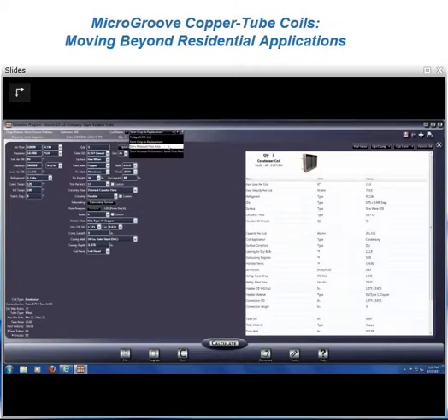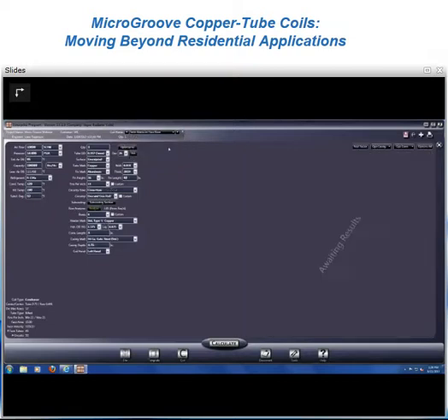Well, one of the things that some of our customers are interested in is, what if I can get the performance in less space, particularly with systems that are in cramped spaces such as mobile applications? That may be something you want to look at. So let's take a look at this. For this installation, I'm still sticking with my same performance, but now I'm going to take 18 inches off the fin length of the coil. I'm going to shrink from 60 inches fin length down to 42 inches.